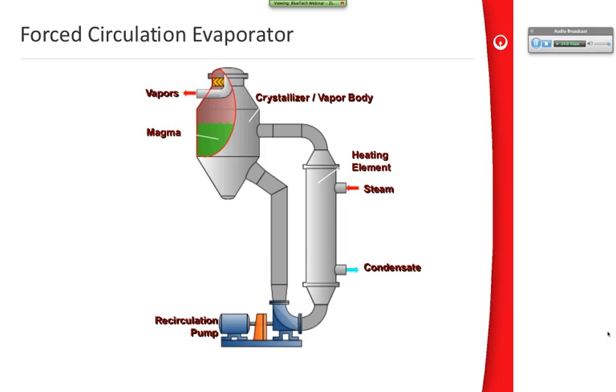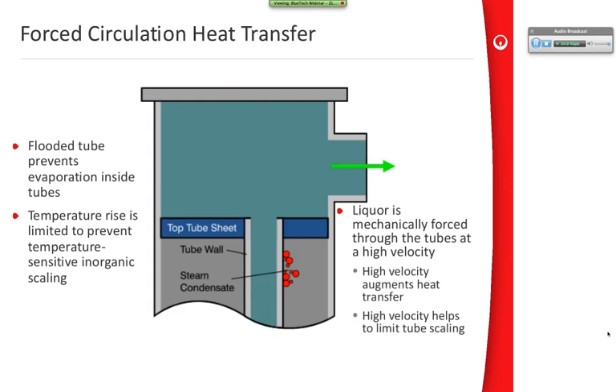Again, the forced circulation evaporator works on the basis that it's a flashing type evaporator. The brine heat transfer surface is flooded. It's always located below the level of liquid in the vapor body, so only sensible heat is transferred in the heat exchanger, and that heat flashes into vapor when the hotter liquid gets to the vapor body. Vapors go through a mist eliminator and exit and go to either a condenser or a compressor.